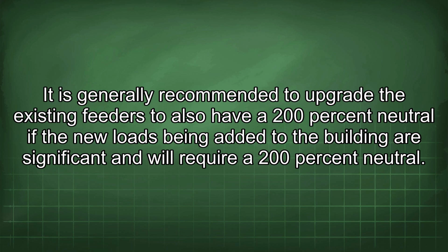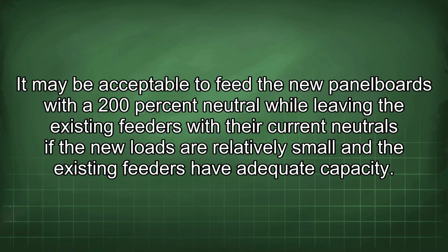It is generally recommended to upgrade the existing feeders to also have a 200% neutral if the new loads being added to the building are significant and will require a 200% neutral. It may be acceptable to feed the new panel boards with a 200% neutral while leaving the existing feeders with their current neutrals if the new loads are relatively small and the existing feeders have adequate capacity.